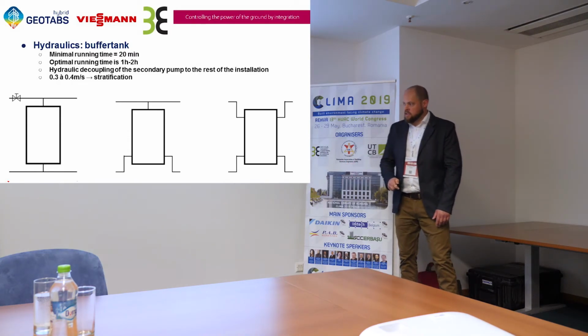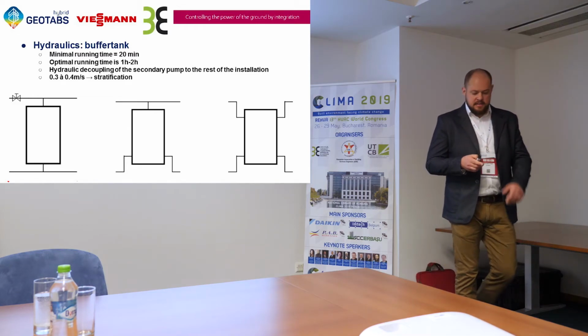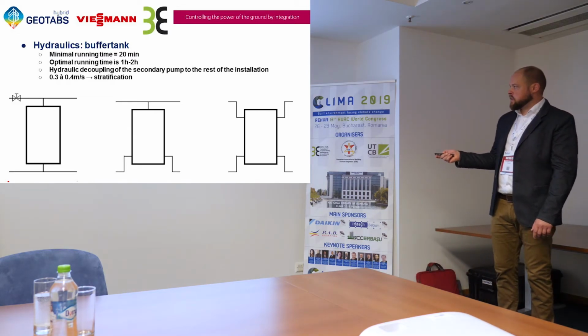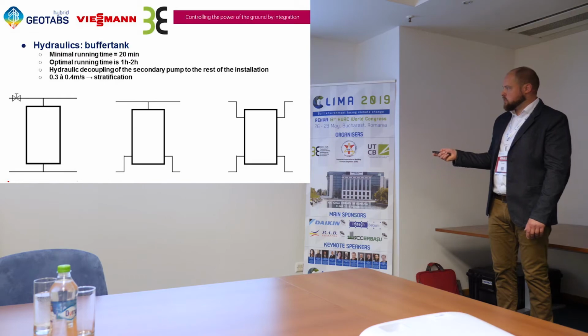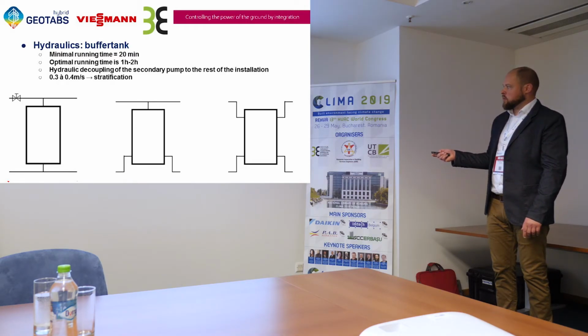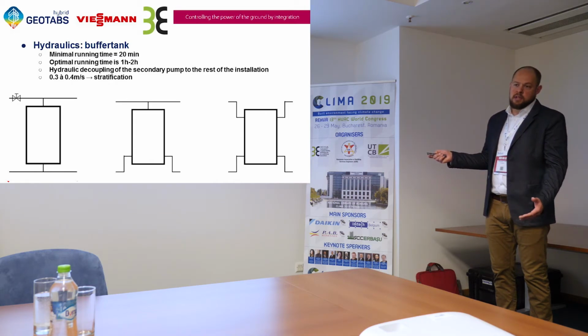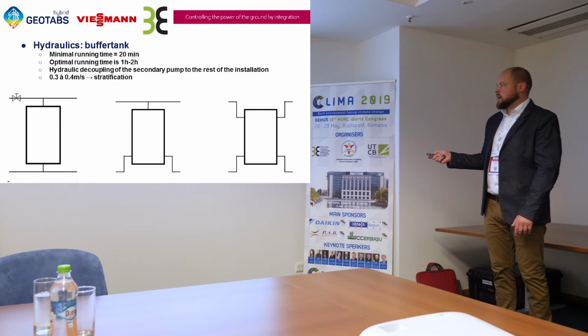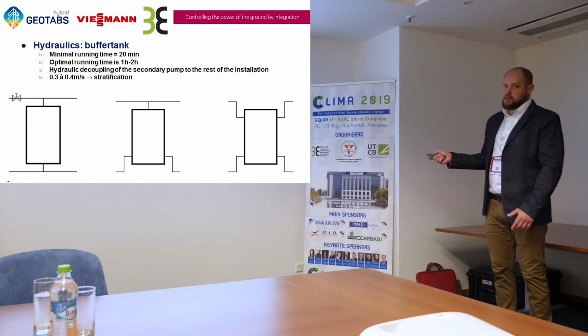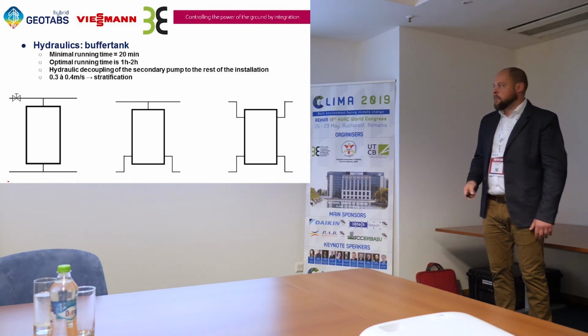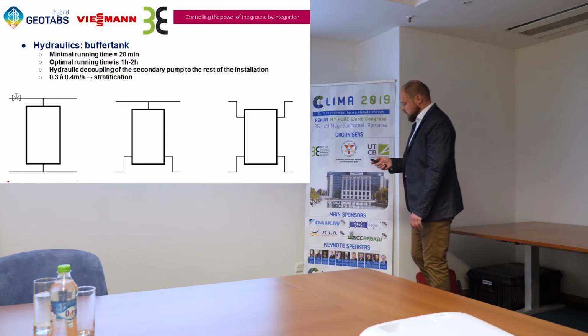What we see with bigger installations, we have high flow rates. You get some mixing of temperature during this process, the transfer here, and that means that the temperature is often lower at this point than at this point. So what will happen? The heat pump has to make a higher temperature here to reach the demanded temperature to the installation, and that means, of course, a loss in COP. So what do we do today?